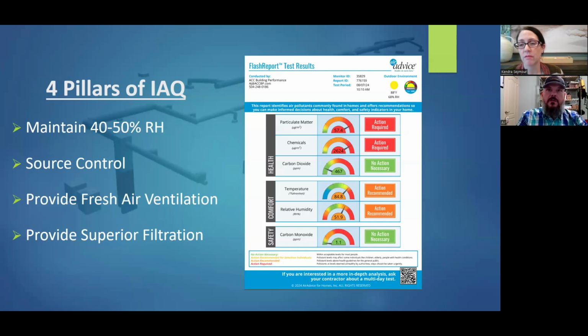He knows how to pressure map a system, and he'll be able to tell you, yes, this system can handle a MERV 13 or MERV 16, or just the opposite. If you have a MERV 16 and he goes out there, or she, and the system's running 1 inch of static pressure, then no, that system can't handle that MERV 16 filter. Yeah, that's good to know.